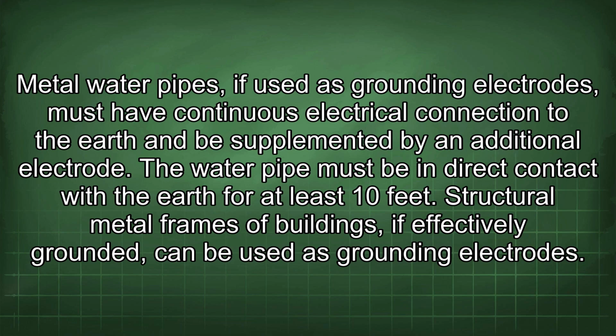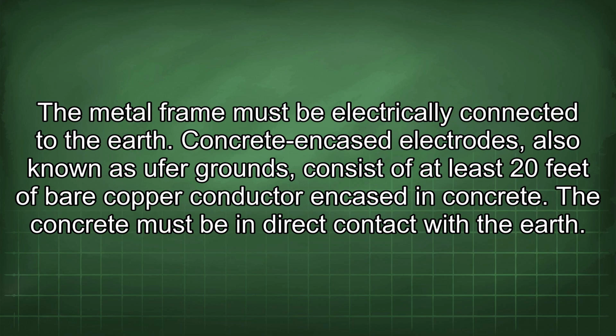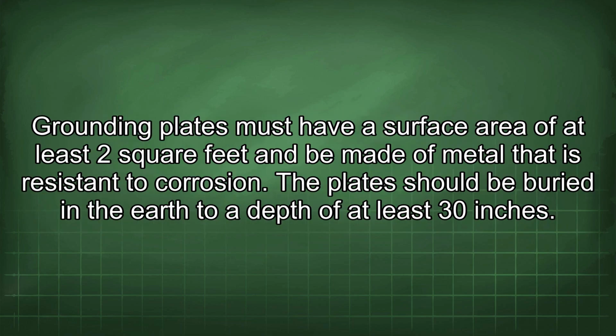Structural metal frames of buildings, if effectively grounded, can be used as grounding electrodes. The metal frame must be electrically connected to the earth. Concrete encased electrodes, also known as Ufer grounds, consist of at least 20 feet of bare copper conductor encased in concrete. The concrete must be in direct contact with the earth. Grounding plates must have a surface area of at least 2 square feet and be made of metal that is resistant to corrosion. The plate should be buried in the earth to a depth of at least 30 inches.